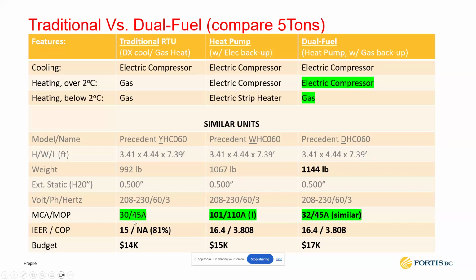But I want you to take a look at the electrical capacity. The electrical capacity of the traditional rooftop unit is very similar to the dual fuel. In comparison, the fully electrical rooftop unit will require 2 to 3 times more electrical capacity. This makes it a very good option for a one-to-one replacement. You will have to consider the additional weight, and obviously the additional cost is a factor to consider, but that's where we came in.